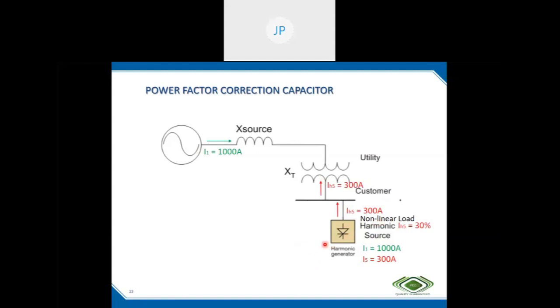It produces fifth harmonic 30%. For simplicity of evaluation, we are considering only the fifth harmonic. So for a 1000 amps load, 30% of it is fifth harmonic, 300 amps, injecting into the system. So here we have two sources. One source is the nonlinear load, a current source, and its symbol is as shown here. This is a voltage source, this is a current source. So two sources are supplying this branch current.